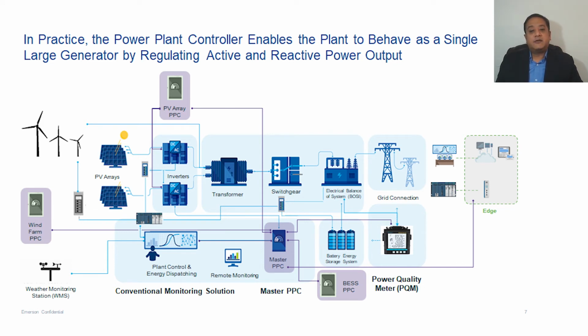Let's go through how the master PPC governs the output of the plant. The master PPC takes the power quality parameters from the PQM meter and makes a determination, based on either its set point or instructions from the operator or the grid, as to what the actual output should be.